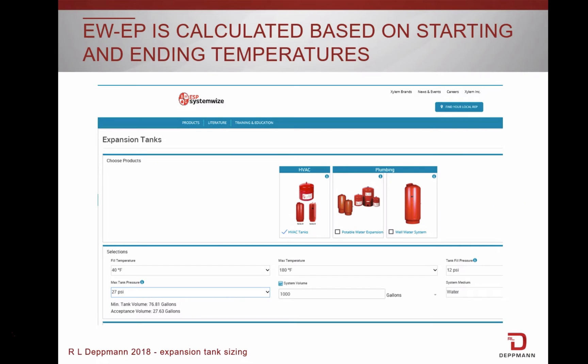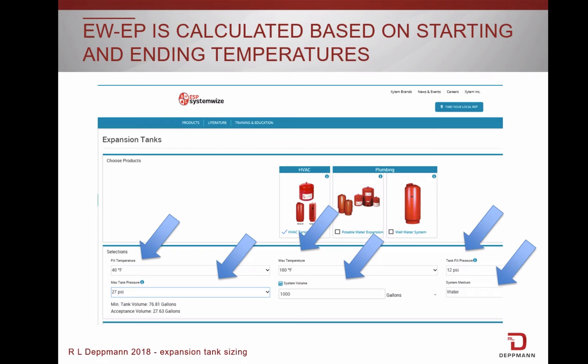When sizing an expansion tank, you will need the following information: fill temperature, maximum temperature, fill pressure, maximum pressure, volume from your design, and the type of fluid in the system. In a compression tank, the initial pressure is atmospheric. In a bladder or diaphragm expansion tank, the initial pressure is the same as the fill pressure.